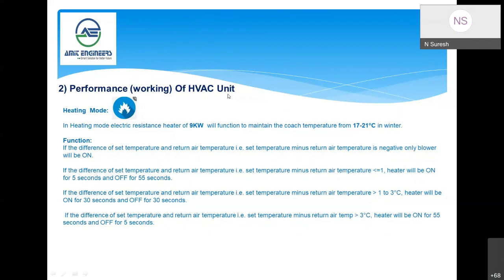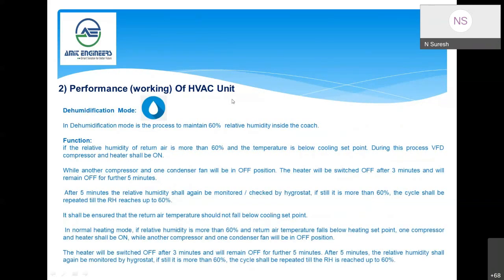Basically, what is happening in cooling mode is a dehumidification mode. Dehumidification is basically to remove the moisture vapors in the air, to maintain less than 60% RH to give human comfort. If the relative humidity of the air is more than 60% and the temperature is below the cooling set point, then during this process the VFD compressor and heater will be on. There is a dehumidification process where one compressor and simultaneously the heaters also will be on to have the post heating.